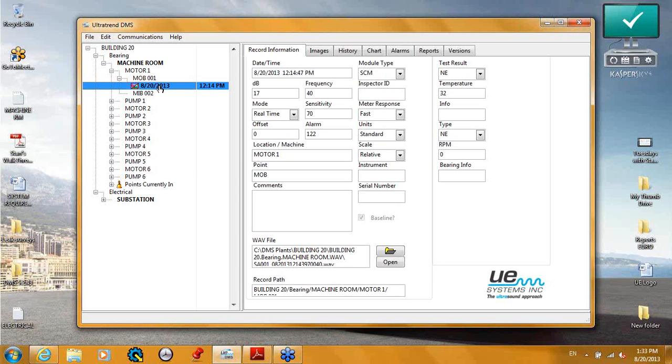Well, the 3,000 is different from all the other digital instruments because the communication only goes one way. With the 9, 10, or the 15, you have the ability to create a route and upload that route, but you can't do that with your 3,000. The communication only goes one way. The 3,000 is basically built for people using it for, let's say, air leak surveys, gas surveys, and so on. So what they'll do is take the instrument out in the field, look for those leaks, and collect dBs from all the leaks they find. Basically all they have to do is create just a group level of where you were focusing your survey, to dump that information from the 3,000 to that group so that you can create a survey report.